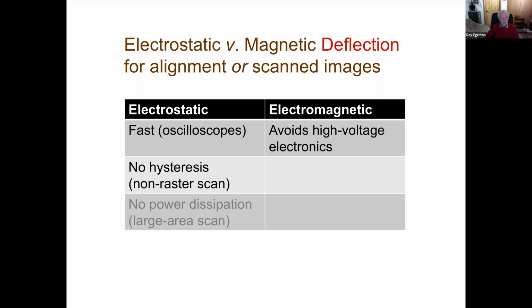But again, there are some advantages of electrostatic fields, particularly if you want to use these deflectors to scan the beam across the specimen. If you want to do that fast, as we know from oscilloscope use, you can scan much faster with electrostatic fields than with magnetic fields. And there is no magnetic hysteresis, which would be valuable if you want to have some kind of non-raster scan. Also, no power dissipation if you have electrostatic scanning, which might be useful if you want to scan over a large area at low magnification.